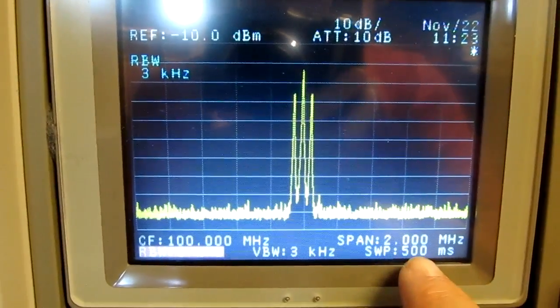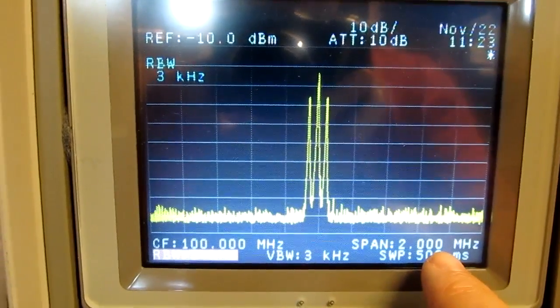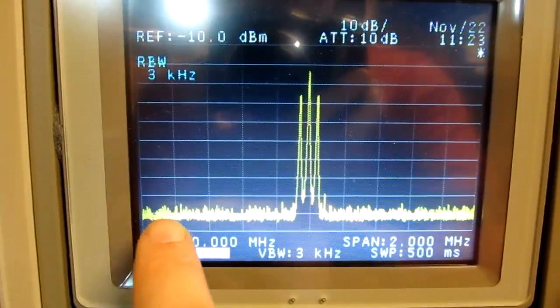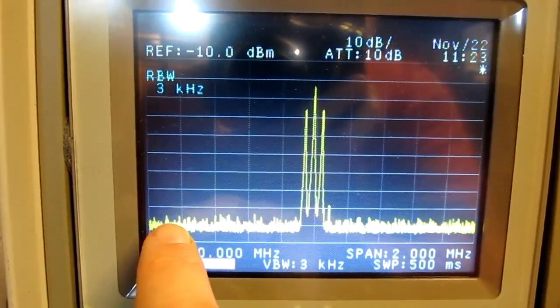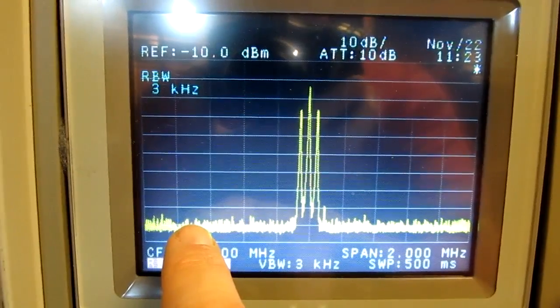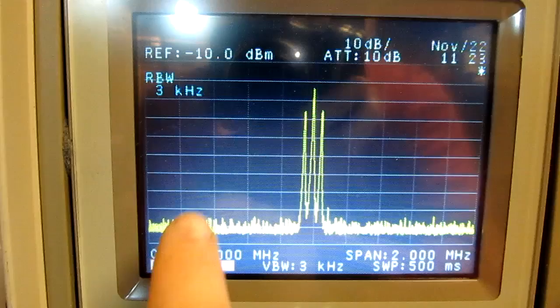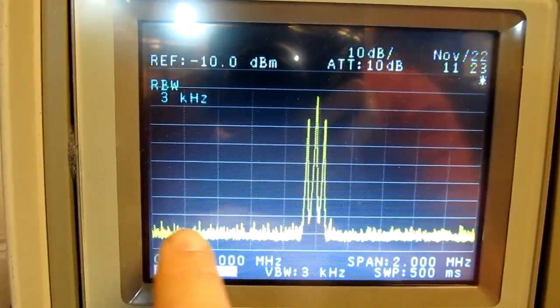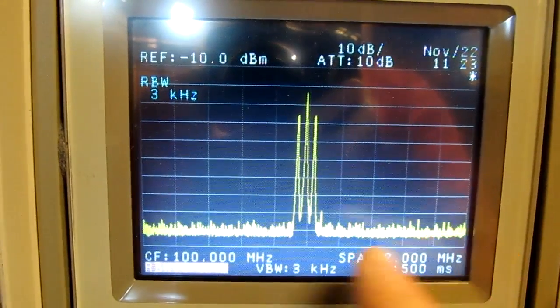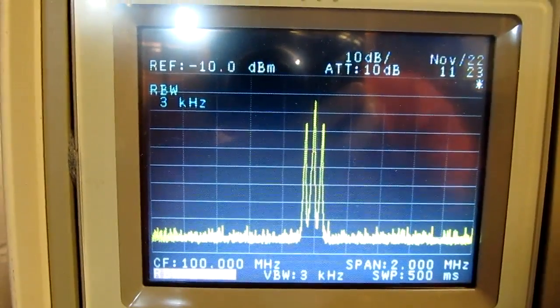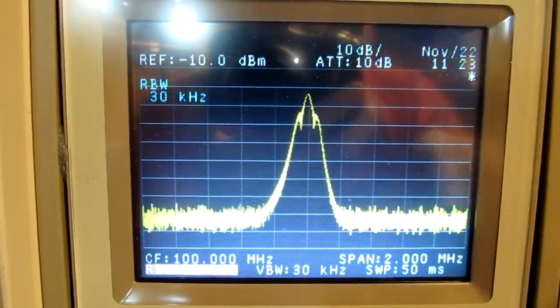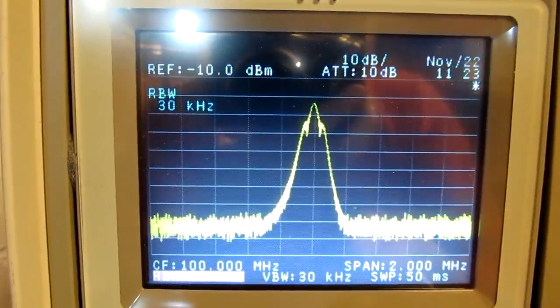You'll also notice that the sweep speed has gotten slower. At the narrow resolution bandwidth you're going to get a slower sweep because the instrument has got to take a sweep slower so it doesn't miss anything. And it has to give the narrower filter time to charge. That's why narrow resolution bandwidths lead to longer sweep times. Otherwise we'd use it all the time. So that's what resolution bandwidth looks like on the spectrum analyzer.